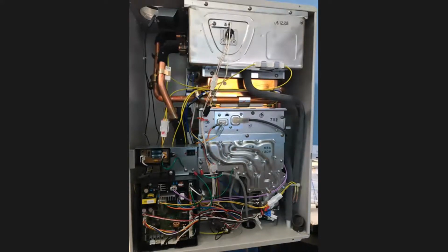On 4-inch venting, we can take this up to 100 feet. On 3-inch venting, we're going to limit to 70 feet. So important to keep that in. And again, no more than 5 elbows. And those are the things that you can run into.